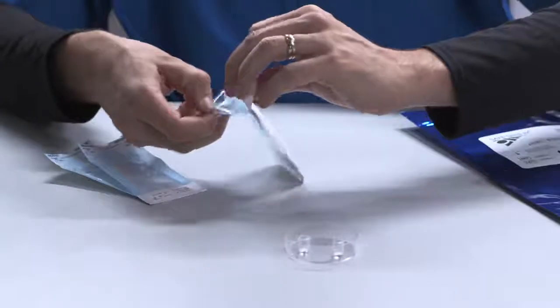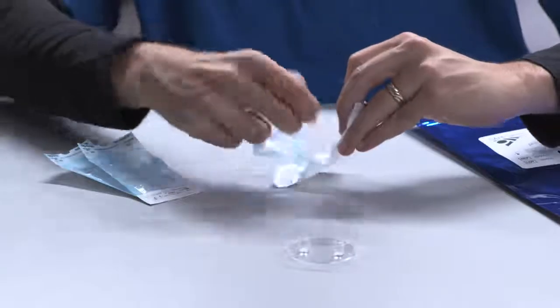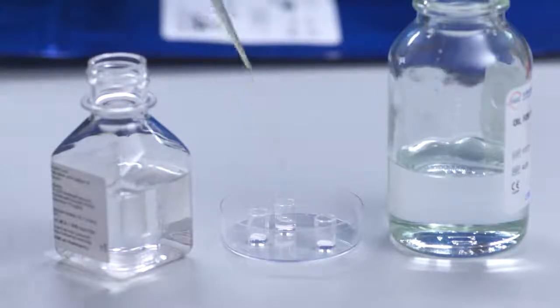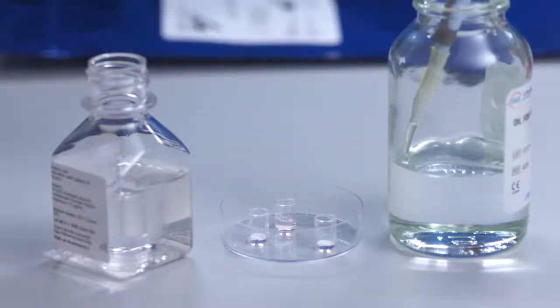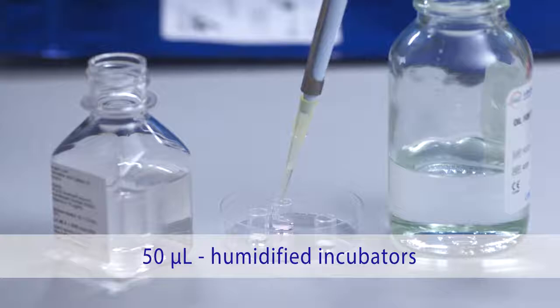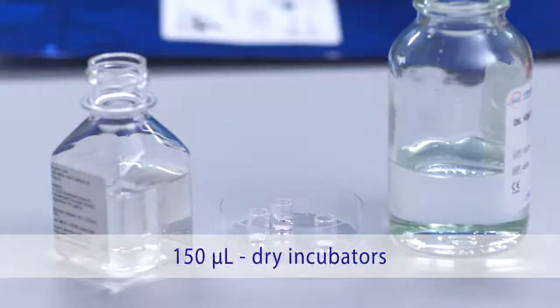For the setup work, open the required number of sensor packages and place them in a Petri dish. Then, carefully pipette 100 microliters of media onto each of the sensor membranes. Be careful not to introduce bubbles while pipetting. Then, add oil to each sensor. Add 50 microliters of oil for humidified incubators and 150 microliters of oil for dry incubators. The oil stays on top of the media and prevents it from evaporating during normal pH monitoring. It is important that the oil fully cover the media. Additional oil can be added if needed. Now, you simply place the sensors into the incubator environment and allow them to equilibrate for 24 hours.